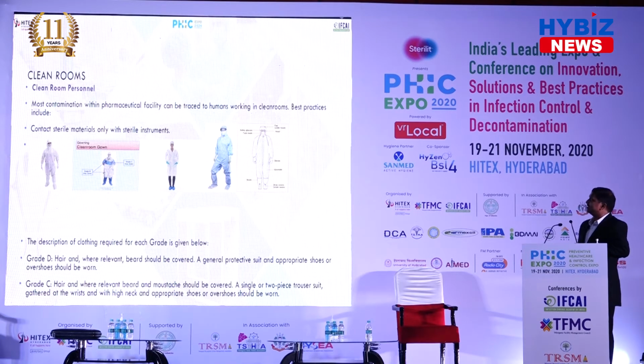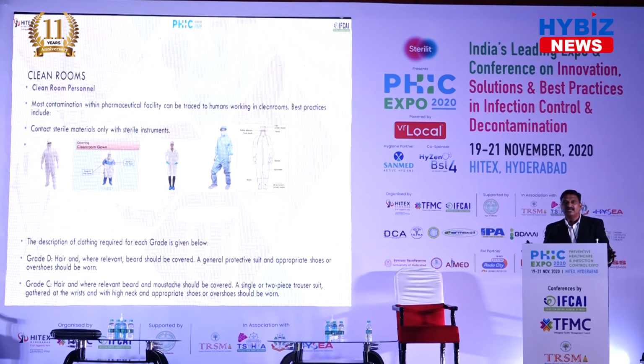Clean room personnel. The most contamination in the clean room is attributed to the personnel present. So the best practices shall be: contact the sterile materials with sterile instruments only, walk slowly and deliberately, don't come in the path of unidirectional airflow, and so on.